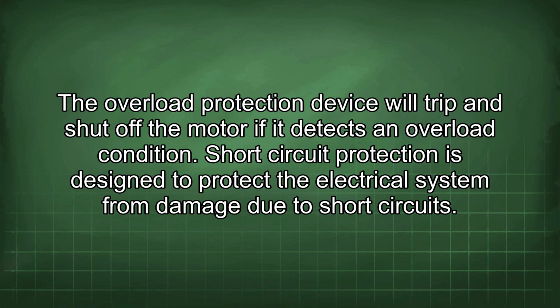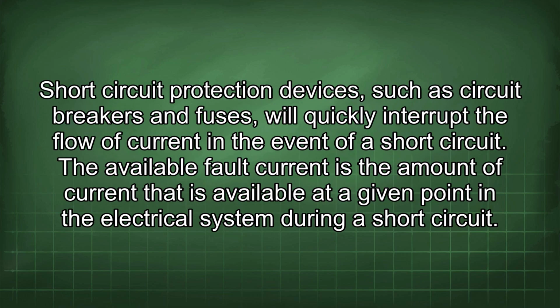Short circuit protection is designed to protect the electrical system from damage due to short circuits. Short circuit protection devices, such as circuit breakers and fuses, will quickly interrupt the flow of current in the event of a short circuit. The available fault current is the amount of current that is available at a given point in the electrical system during a short circuit.